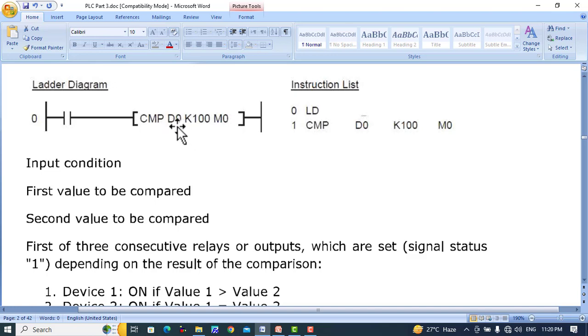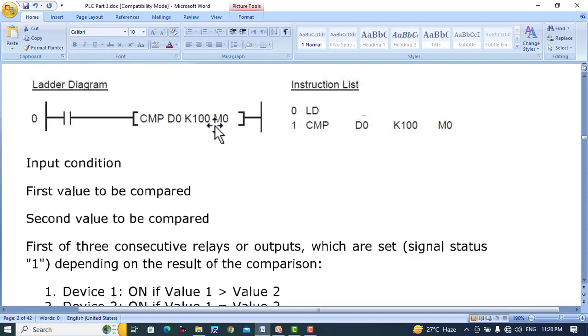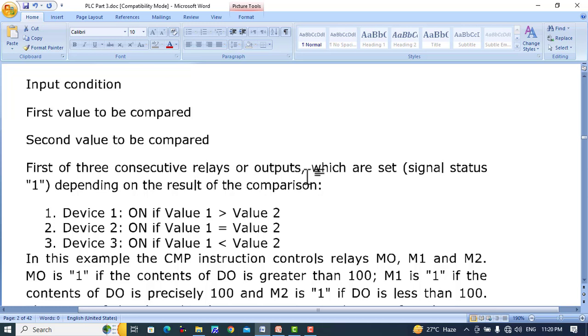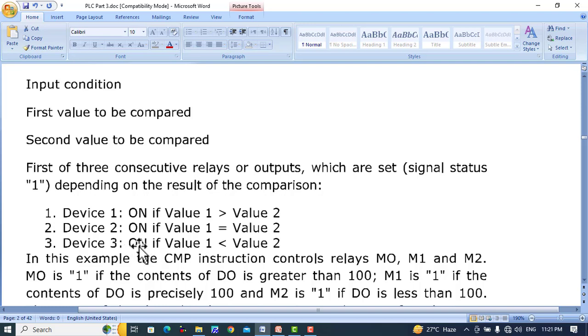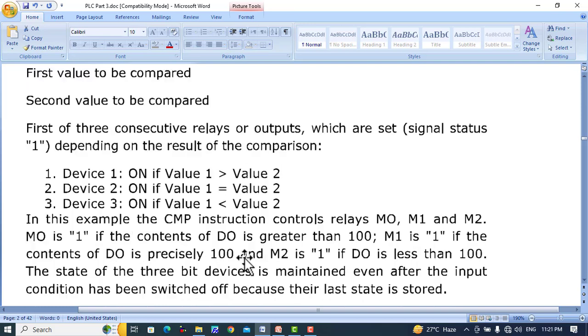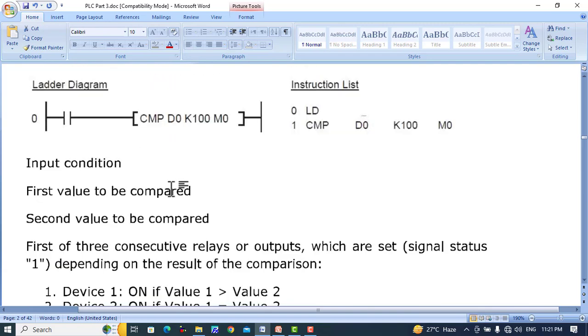CMP compares two values across three consecutive relay outputs. If D0 is greater than K100, it will set relay M0. If D0 is equal to K100, it will set relay M1. If D0 is less than K100, it will set relay M2. Device one (M0) turns on when value one is greater than value two, device two (M1) turns on when values are equal, and device three (M2) turns on when value one is less than value two.